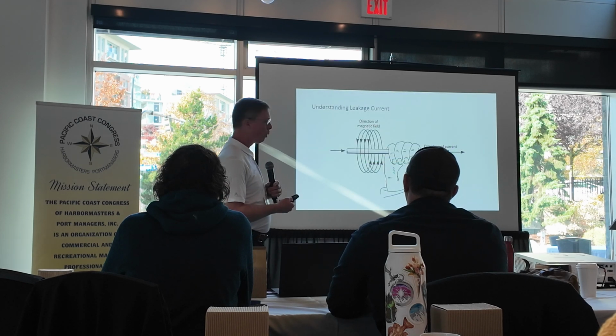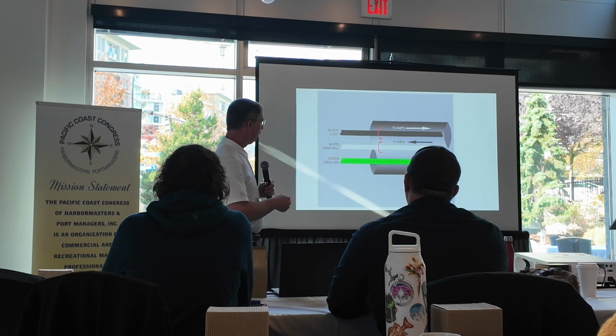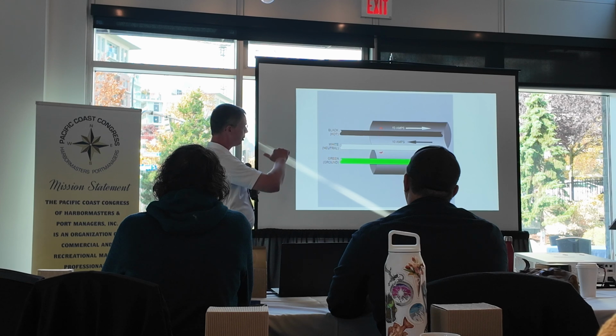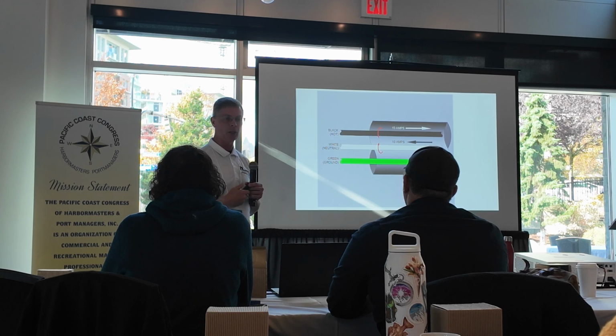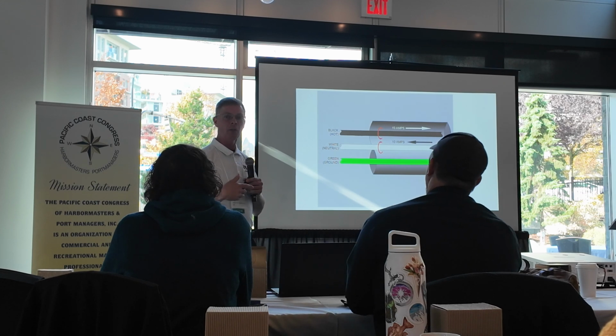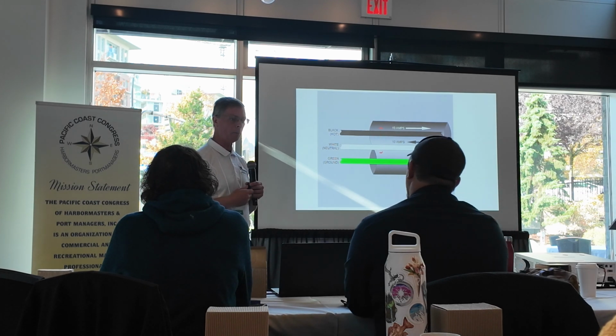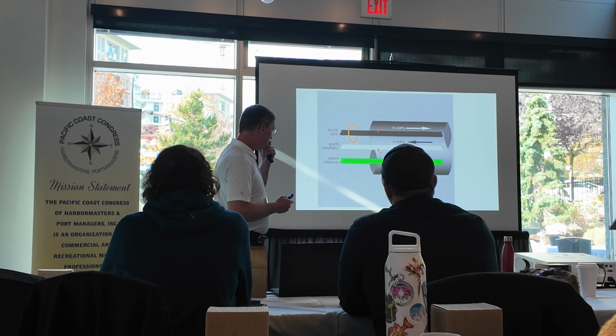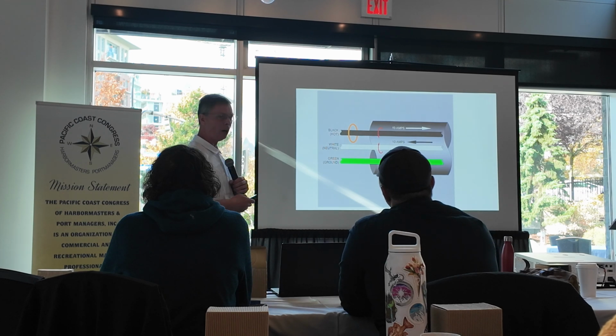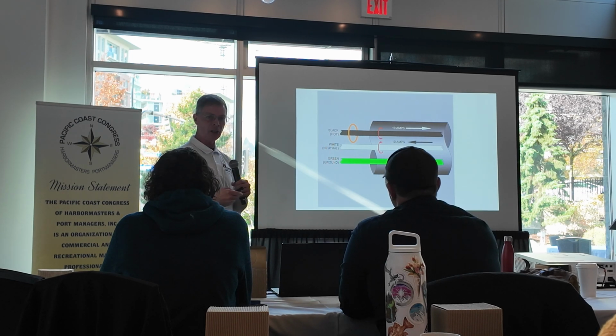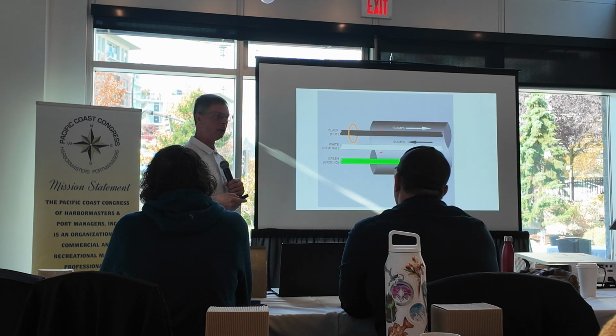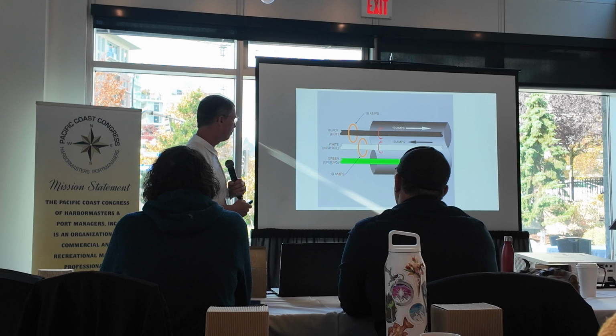That's the right-hand rule. Well, what if you turn that around and you put your thumb in the other direction? Which way is that magnetic field rotating? In the opposite direction. But it's still magnetic field that you clamp around. The white wire is 10 amps. If I clamp around that black wire, I'll measure the intensity of the magnetic field, which is displayed in amps, and so it'll be 10 amps. So if I clamp around the white wire, I'd also see 10 amps.